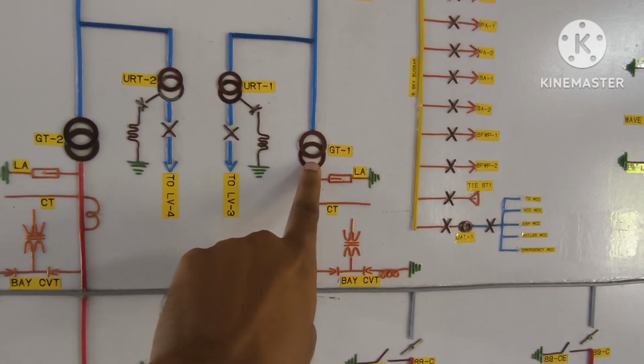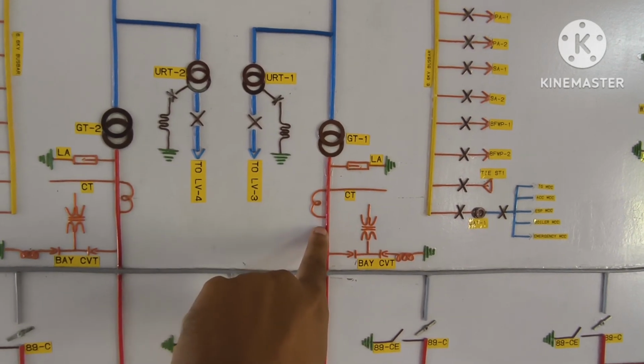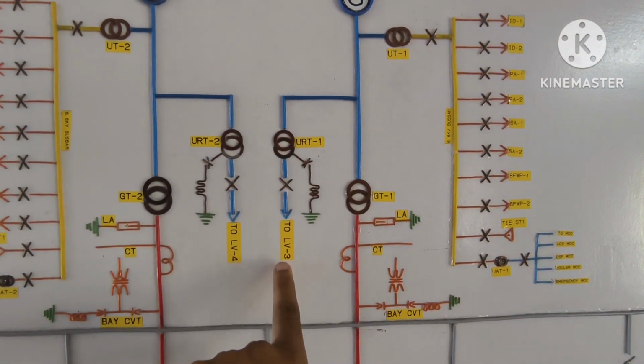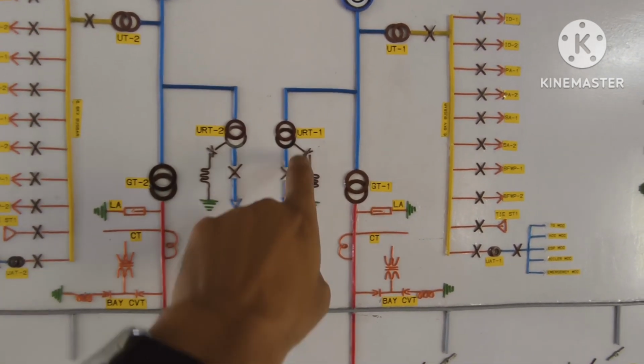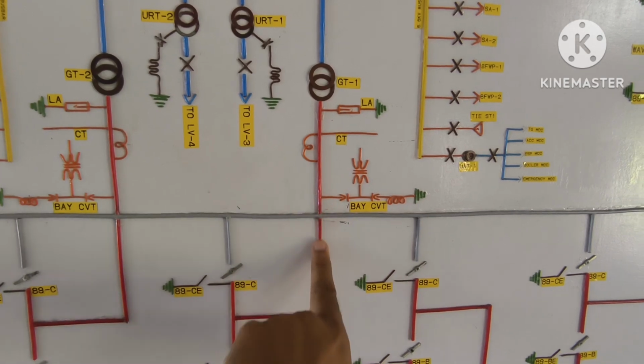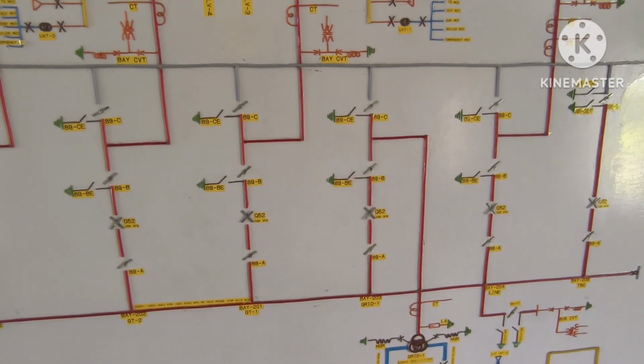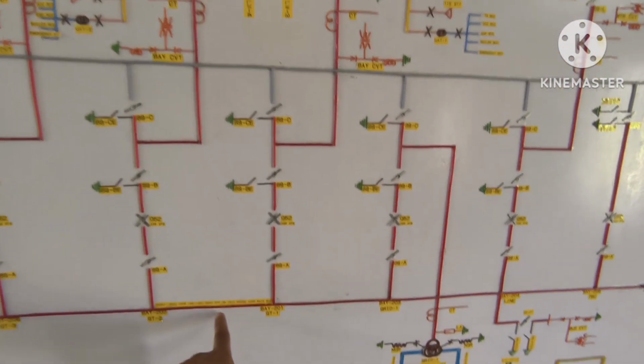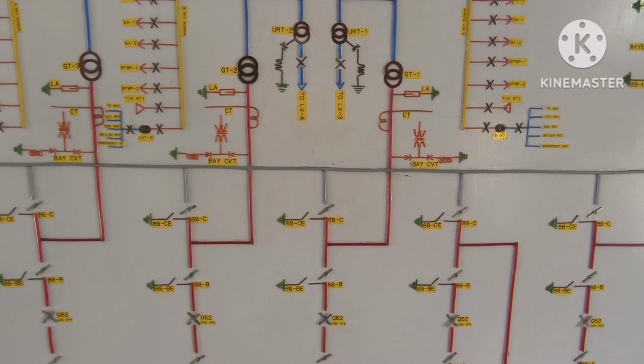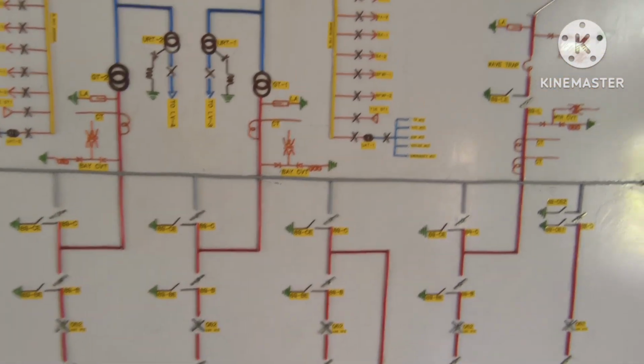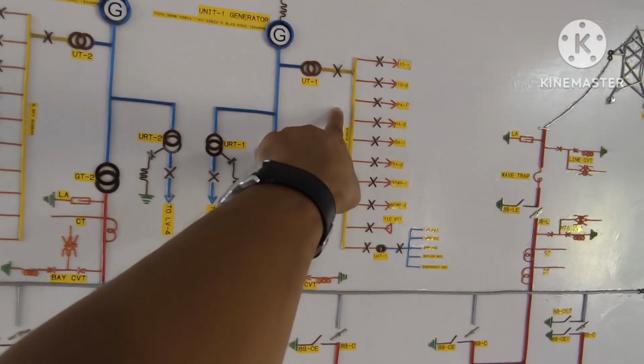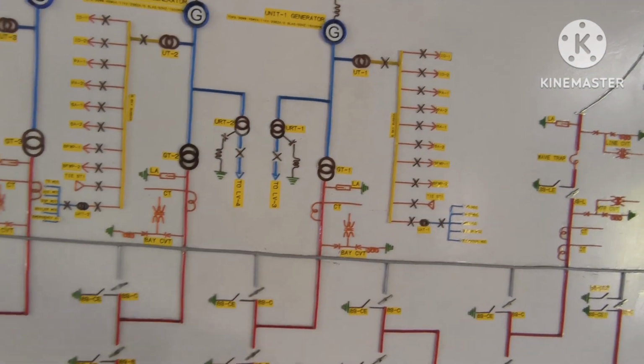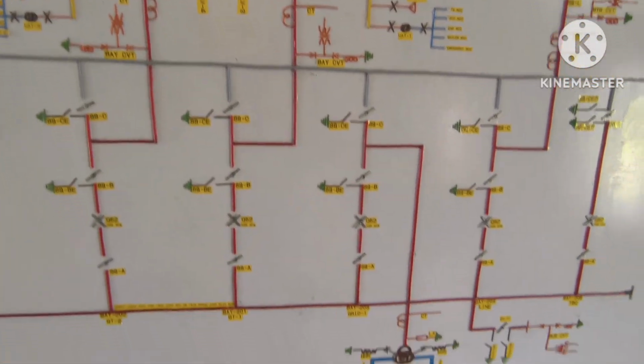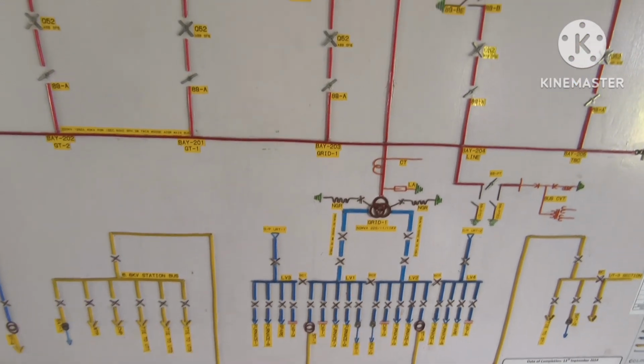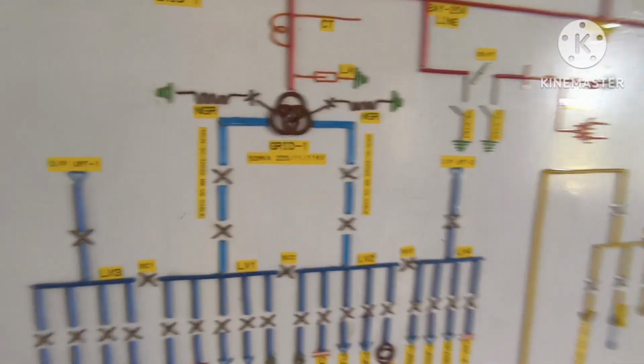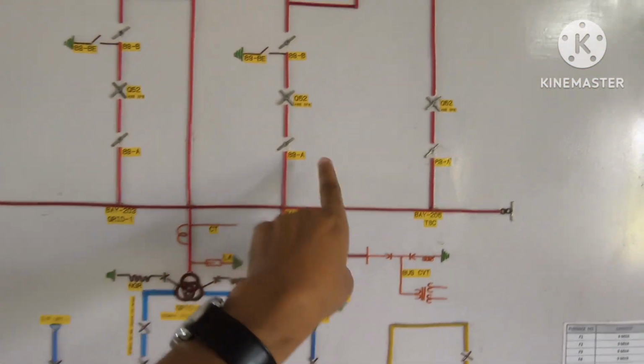Next, if you see, it is the generator transformer, which will step up to 220 kV, and this is the tapping for the unit ratio transformers, 11 by 11.5 kV. The red color indicates 220 kV. Our total switchyard is 220 kV, connected to main and transfer bus systems. All red cables indicate 220 kV, and the gray color indicates 220 kV that is not charged. Whatever generation is there, after the UAT and URT1, the remaining power we inject to the bus, and through the grid transformer or the auxiliary transformers we utilize it for our captive production, and the remaining power we export to the grid.